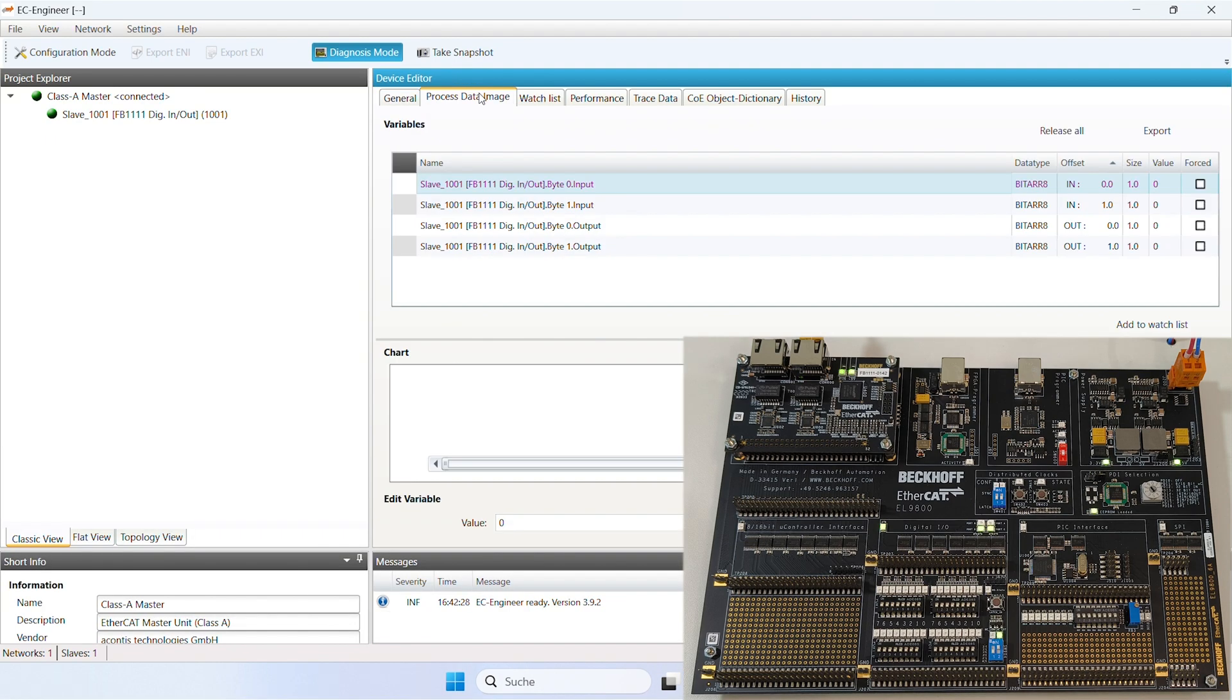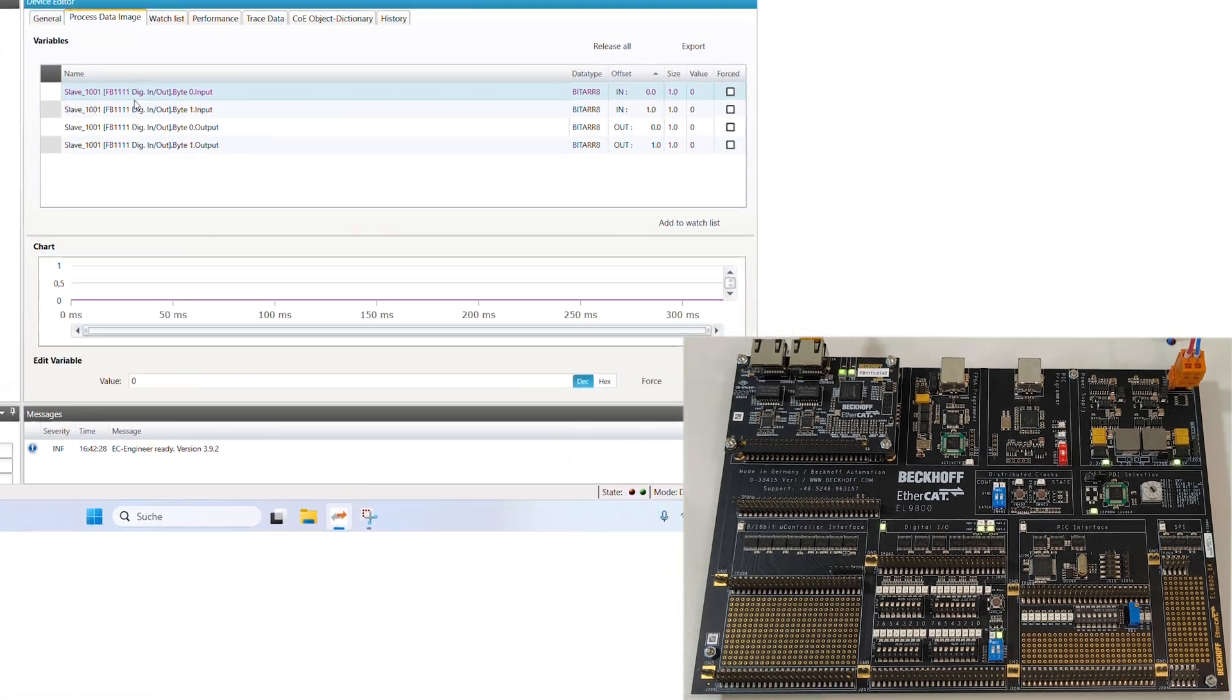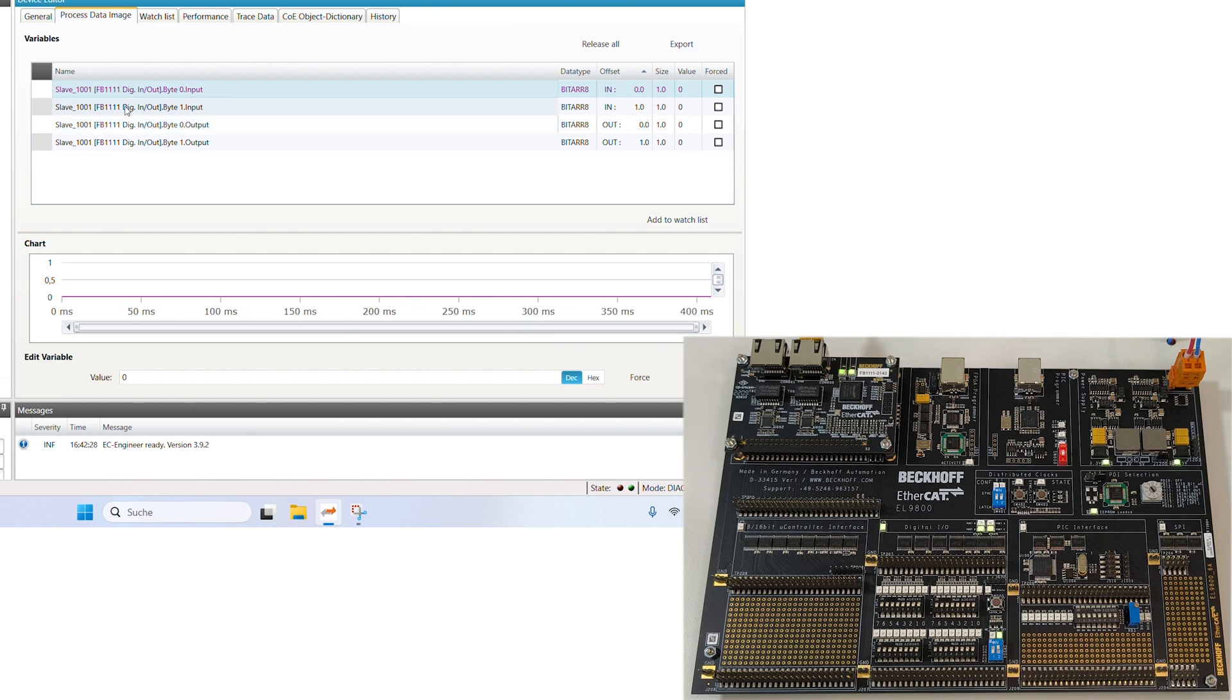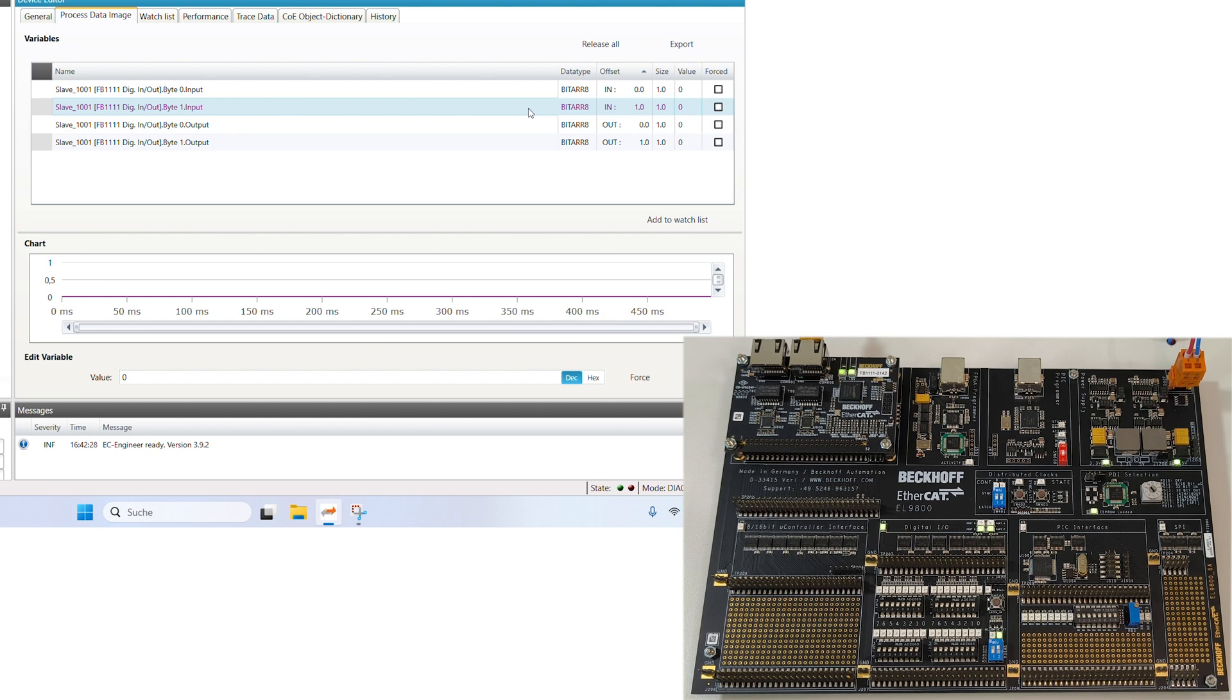EC-Engineer can remotely change the EtherCAT state and this can be observed by the LED pattern on the sub-device. It is also possible to verify communications by toggling some switches on the sub-device and observing the process data variables changing in the EC-Engineer user interface.